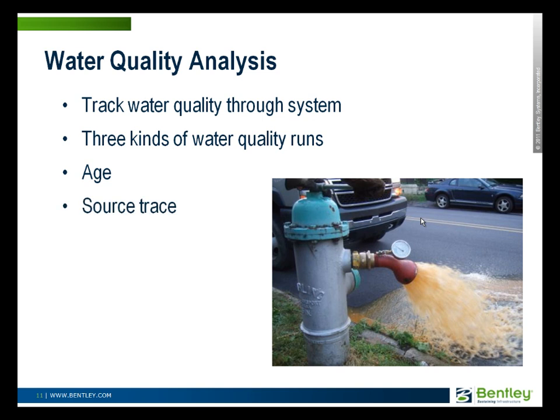You can also trace the source of water, which is especially important in systems that have multiple sources — you want to know which users get water from which sources. A lot of times this is surprising: you would think that water from one source gets to certain users and water from another source gets to others, but when pumps cycle on and off with intermittent operation, the water sloshes around the system a lot more than you'd expect. The final kind of water quality analysis is actually tracking constituents through the system — these can be conservative constituents that don't react, or things like disinfectant residual that is involved in reactions as it moves through a distribution system.